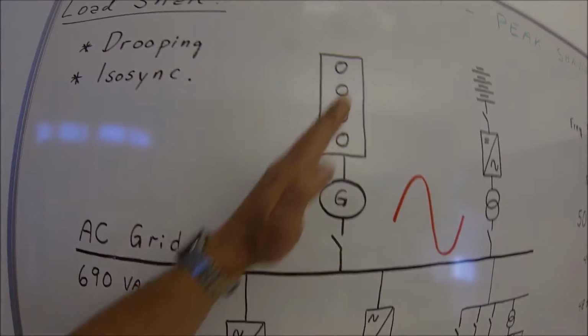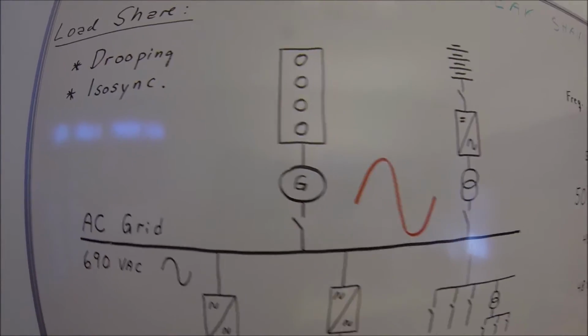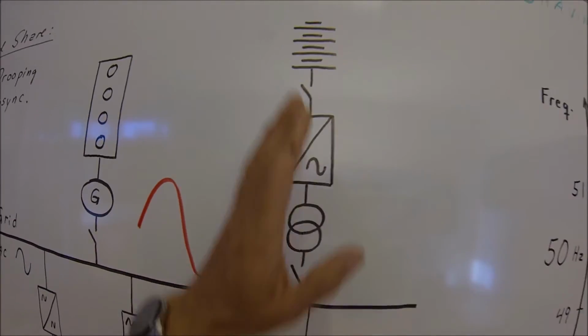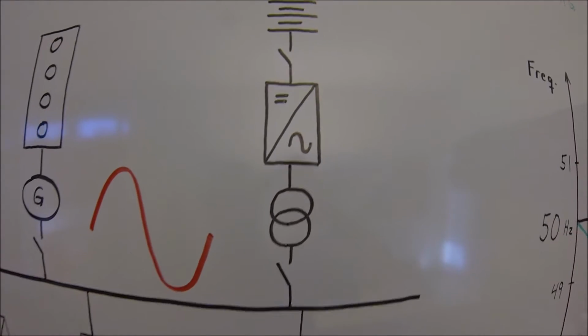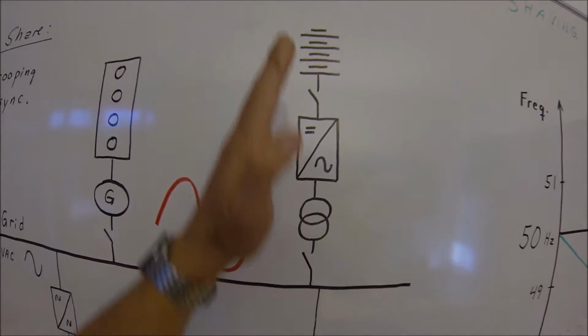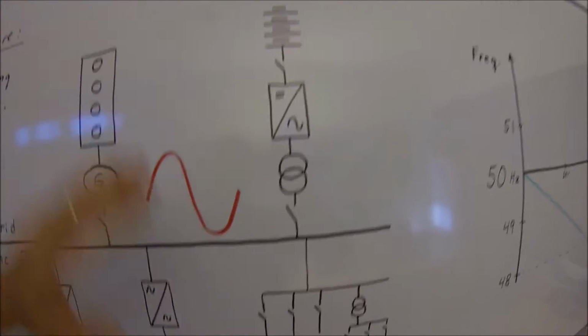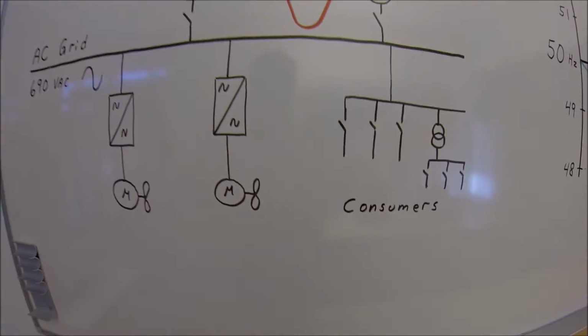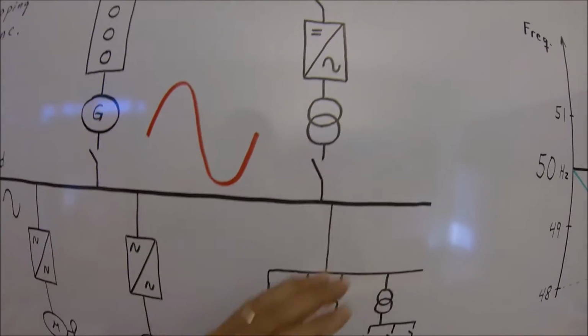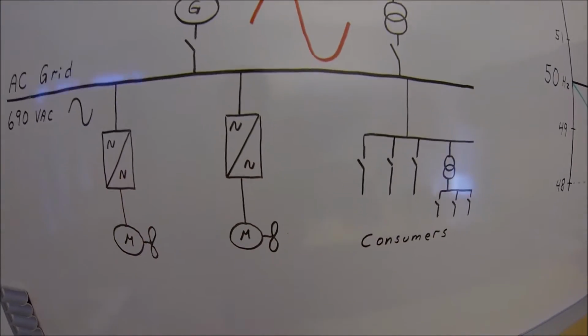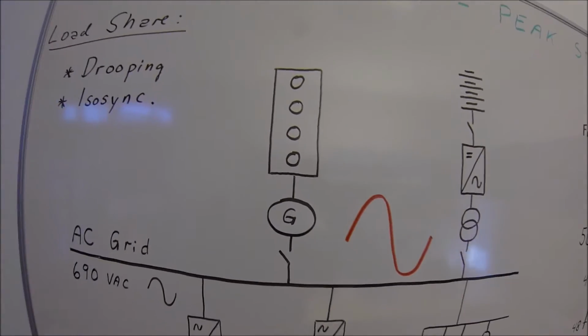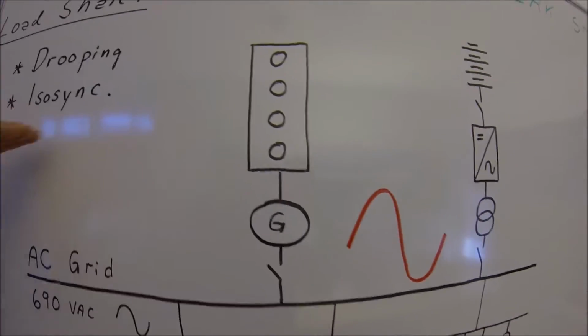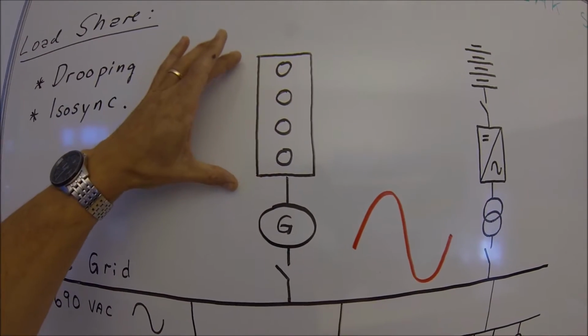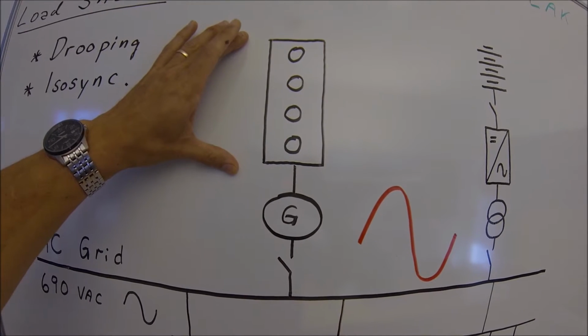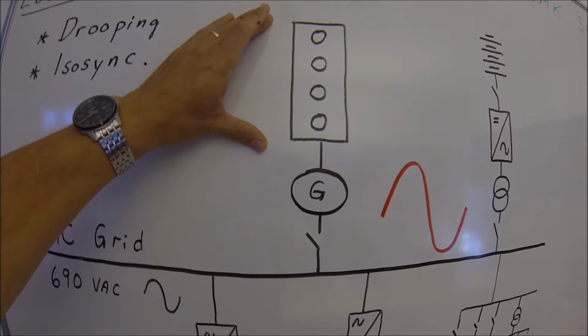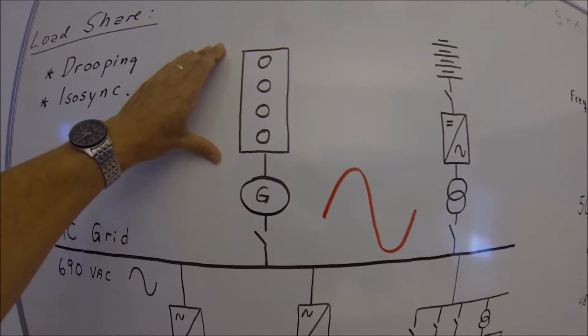They cannot take abrupt changes in load, and abrupt changes in load you will leave to the battery, because that is just electronics. It can take a very rapid increase in load, and also when the consumers reduce the load very fast, you can then charge the battery to emulate the load that was on the grid. The result of this, what you want to achieve, is a very even and nice load on the diesel engines. In that way, the diesel engines can utilize all these environmentally friendly fuels.